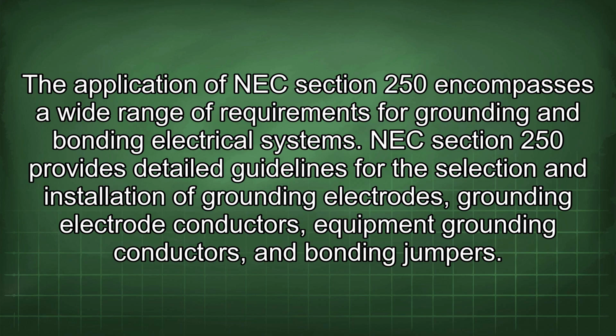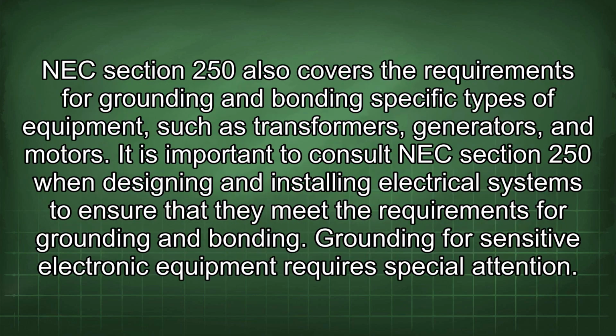The application of NEC Section 250 encompasses a wide range of requirements for grounding and bonding electrical systems. NEC Section 250 provides detailed guidelines for the selection and installation of grounding electrodes, grounding electrode conductors, equipment grounding conductors, and bonding jumpers. NEC Section 250 also covers the requirements for grounding and bonding specific types of equipment, such as transformers, generators, and motors. It is important to consult NEC Section 250 when designing and installing electrical systems to ensure that they meet the requirements for grounding and bonding.